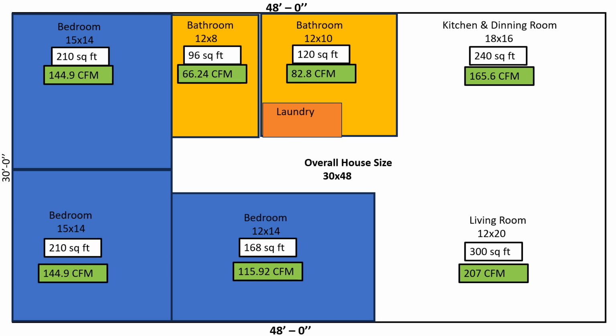And all the ones in the green represent the CFMs required for a 2.5-ton system. So if I took 210 square feet and multiplied that by 0.69, I get 144.9. And that's the one we're looking at right here, the 144.9 CFM to heat and cool that room. Now, same way with the bathroom. If I was using a 2.5-ton, I would do my 0.69, and I would come up to 66 CFMs for the half bath, 82 CFMs for the main bathroom. Bedroom number 3 would be 115, 207 in the living room.